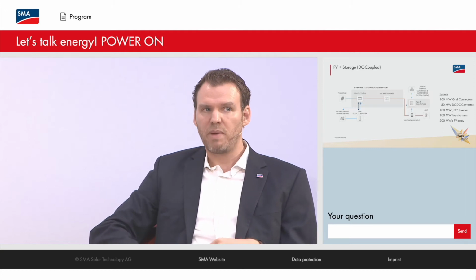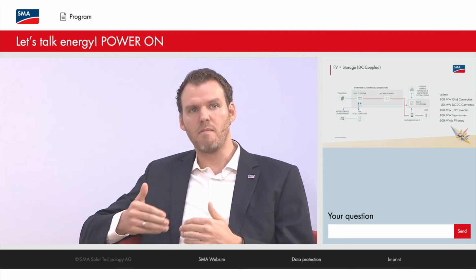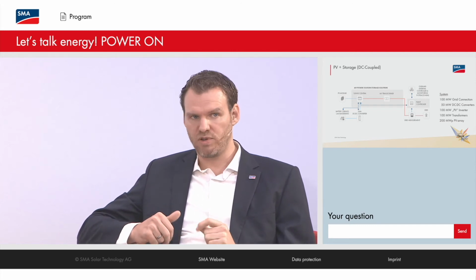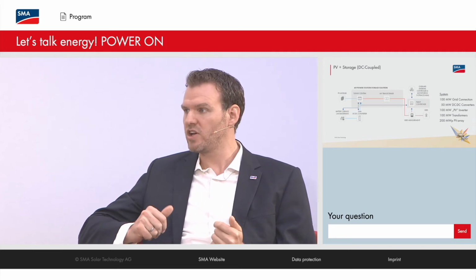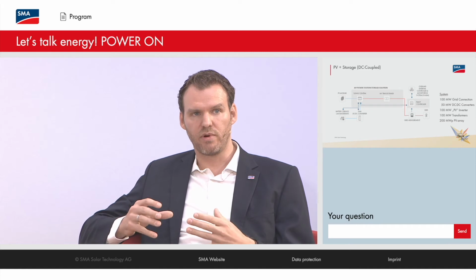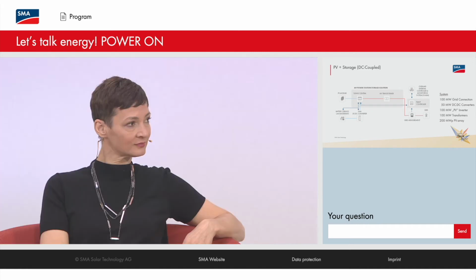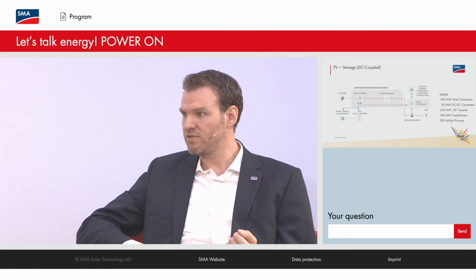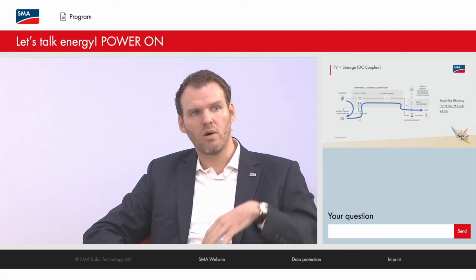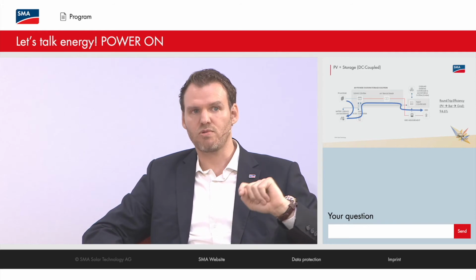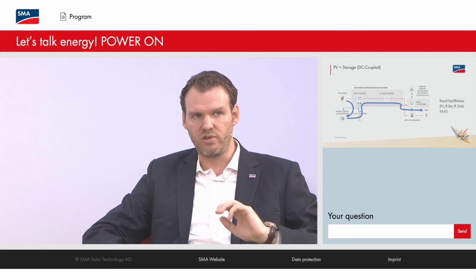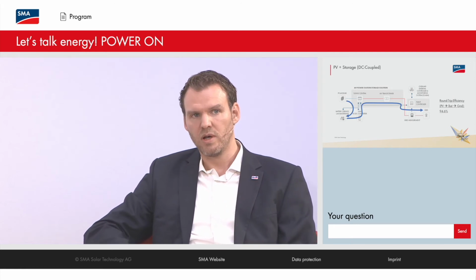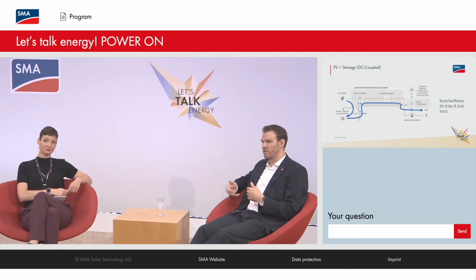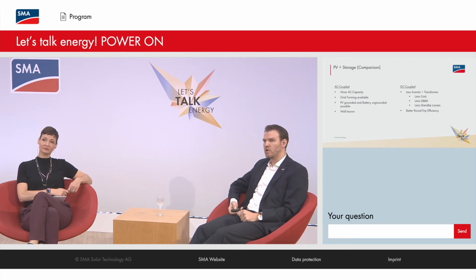So if we compare this with a DC-coupled system, same scenario, we have a 100 megawatt grid connection. So we're adding only 100 megawatt of transformers and inverters. And now we actually add DC-DC converters. And this actually allows us to add a very large PV array to this inverter, whereas the inverter can actually distinguish and can charge the battery and at the same time feed into the network. So that actually allows us to massively reduce the capex of the system, so the cost for the infrastructure. And you also have a certain gain in round-trip efficiency, because now you're actually charging the PV into the battery just through the DC-DC converter. And then from there, you go again through the DC-DC converter, the inverter, transformer, back to the network. So we have a round-trip efficiency somewhere around 94.6%, so more than 3% better, which is pure money basically, really improving this system a lot.